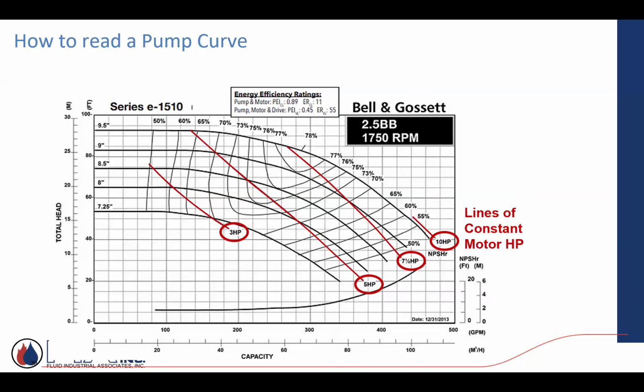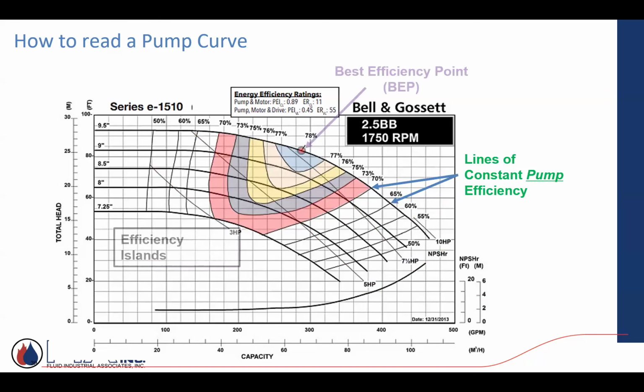Horsepower. What horsepower do I need depending upon the condition? The manufacturer tests it and says, hey, depending upon where you are in these curves and performance, these are the size horsepowers you need to select to get the performance you're looking for. These are what they call the BEP, best efficiency points. So where do you want to pick a pump? Ideally, maybe close to that BEP, but there are standards. You can be a little bit left of that, or you can be a little bit right of that efficiency BEP point.